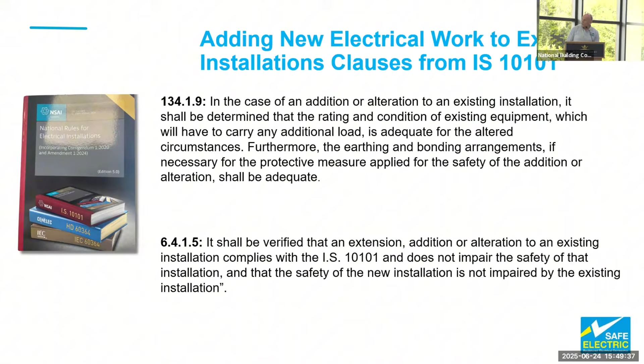So if I just reverse a small bit back to, again, the EV car charger. If I'm installing an EV car charger and my meter tails aren't adequate for that load, now my new installation is going to impair the safety of the existing. So therefore, these are the two key rules that a registered electrical contractor has to perform or undertake before he carries out any installation.